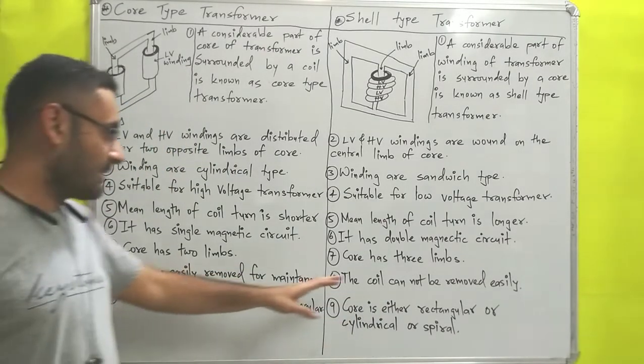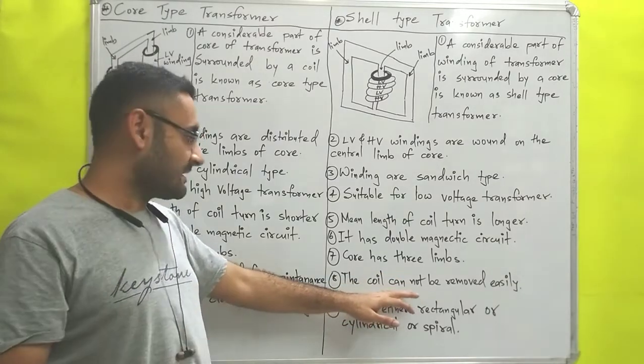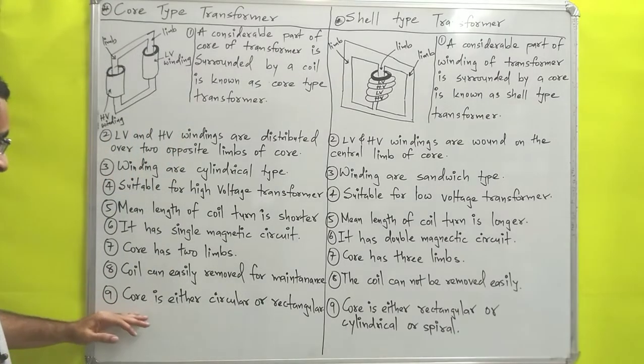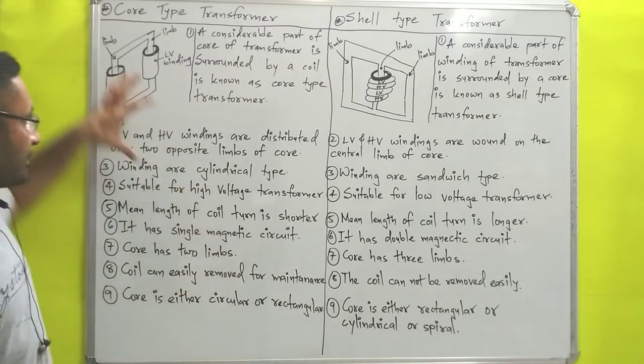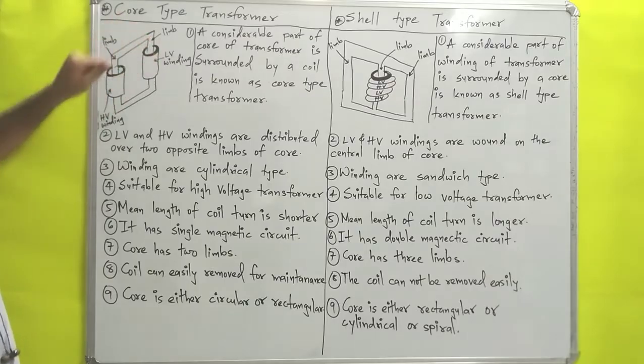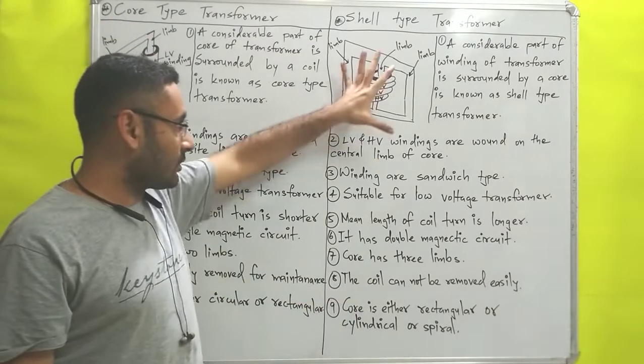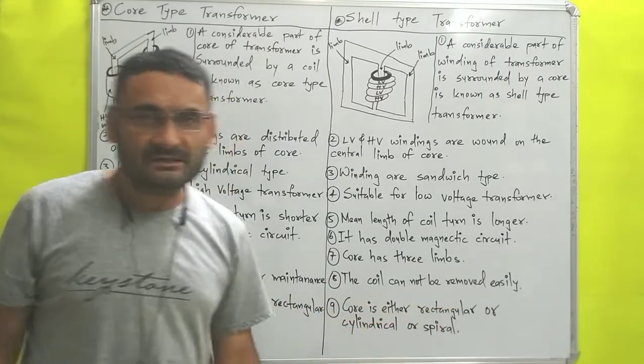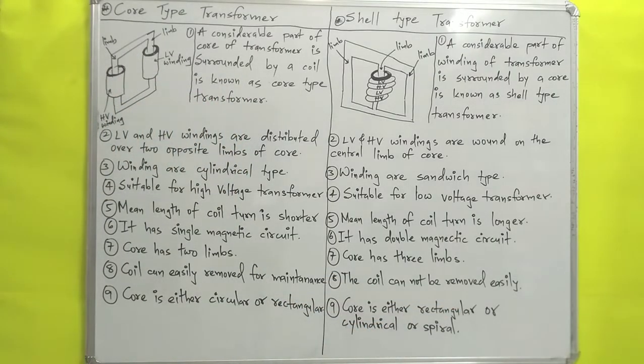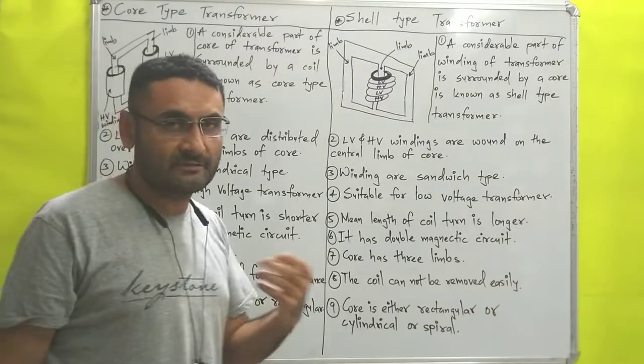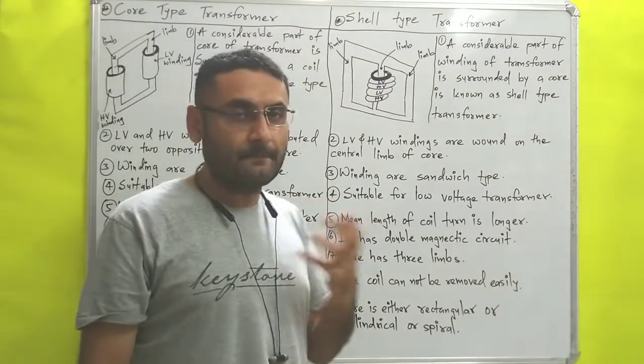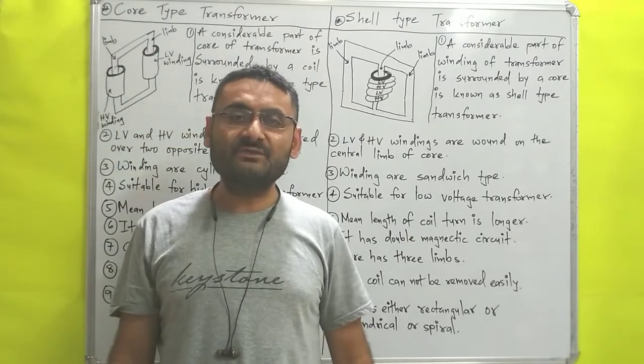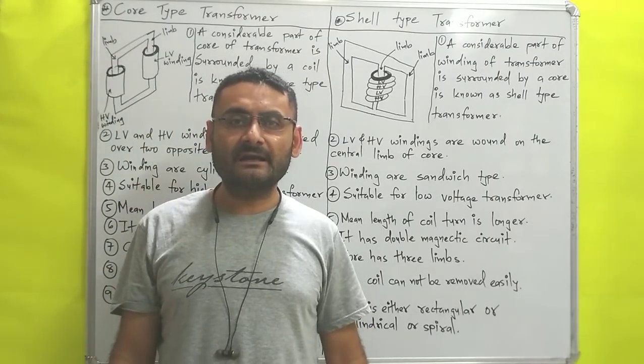The next difference is that in the core type, the coil can be easily removed for maintenance. In the shell type, since the coil is sandwiched, the coil cannot be removed easily. Lastly, the core in the core type is either circular or rectangular, while the core in the shell type can be rectangular, cylindrical, or spiral. That is all about the comparison of core type and shell type transformers. Thank you very much.